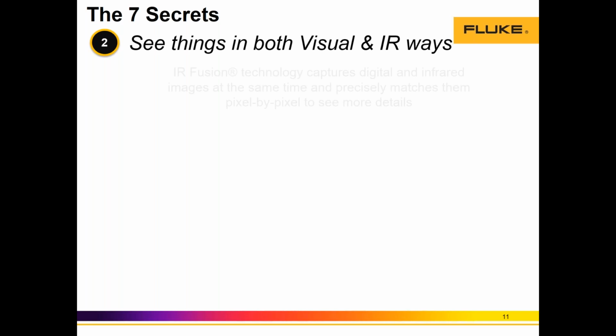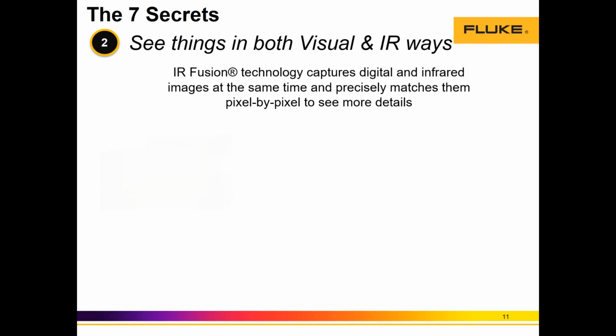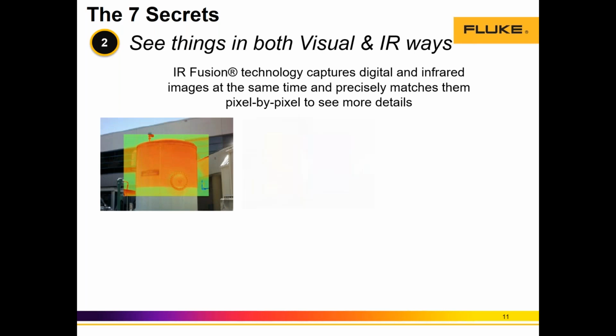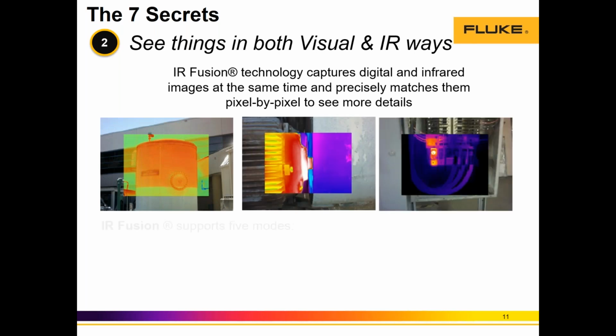So the second secret I want to talk to you about is IR Fusion, overlapping visual with infrared images. Fusion technology captures a visible light image in addition to the infrared image. I define it as taking the mystery out of infrared because it overlaps visual spectrum images with infrared images. Here are 3 examples: a large tank with a low level of liquid, a fused image of a motor, and an electrical panel. Fluke cameras support this technology, called IR Fusion, and we support 5 modes of IR Fusion in most of our cameras.